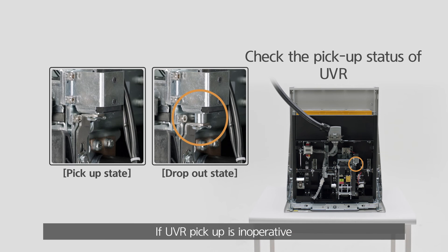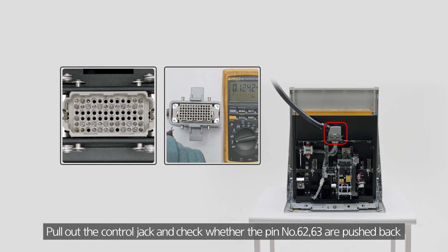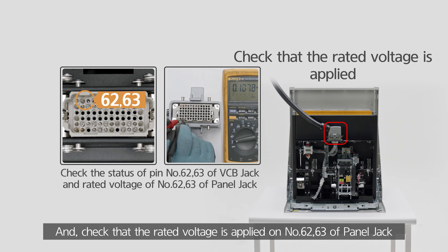If UVR pickup is inoperative, pull out the control jack and check whether pins number 62,63 are pushed back, and check that the rated voltage is applied on number 62,63 of the panel jack.